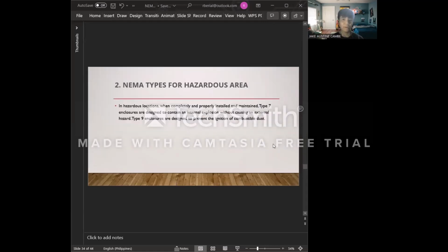So next type of NEMA enclosure is for the hazardous area. Earlier were the non-hazardous types, now these are the types for hazardous areas. In a hazardous location, when completely and properly installed and maintained, type 7 enclosures are designed to contain an internal explosion without causing an external hazard. While type 9 enclosures are designed to prevent the ignition of combustible dust.